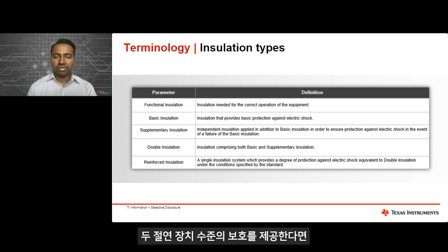And double insulation is insulation that comprises both basic and supplementary. If a system has both basic and supplementary insulation, then the system is said to have double insulation. And lastly, reinforced insulation is a single insulation system which provides a degree of protection against electric shock that is equivalent to double insulation under the conditions specified by the standards. If instead of 2 insulation devices, we use one isolator that is offering the protection of the 2 insulation devices, that device is said to be offering reinforced insulation.